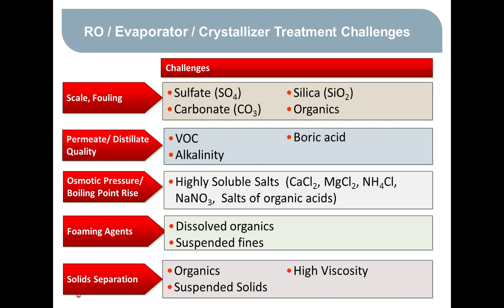Highly soluble salts that don't really want to come out of solution tend to impede the separation process of getting the dissolved solids from the water, because they increase the osmotic pressure in an RO system and they increase the boiling point elevation in a thermal system. Those salts are typically highly soluble chloride salts like calcium chloride, magnesium chloride, ammonium chloride, or nitrate salts, or salts of organic acids, acetates and formates. Those salts tend to not want to come out of solution. They tend to build up and they tend to increase the resistance to heat transfer or osmosis in the concentration systems that we use in ZLD.